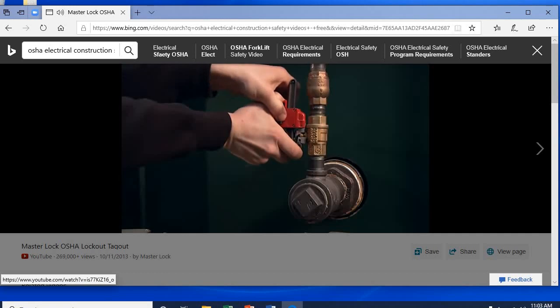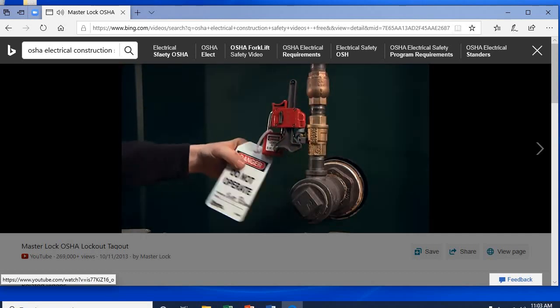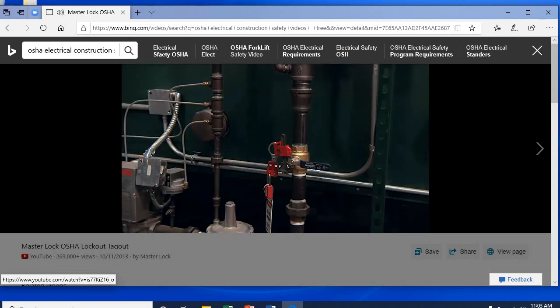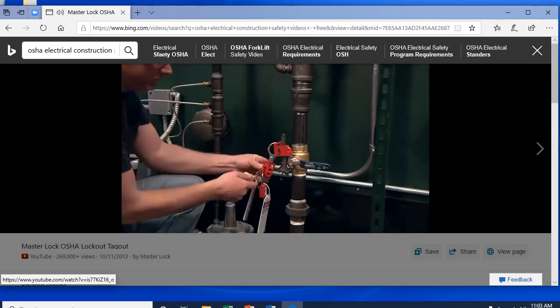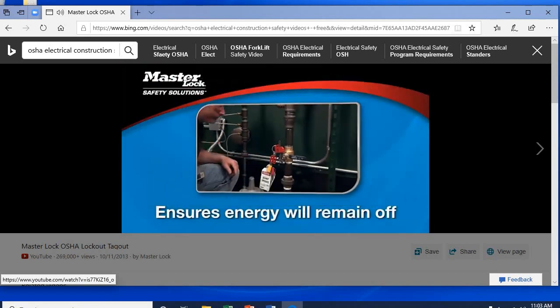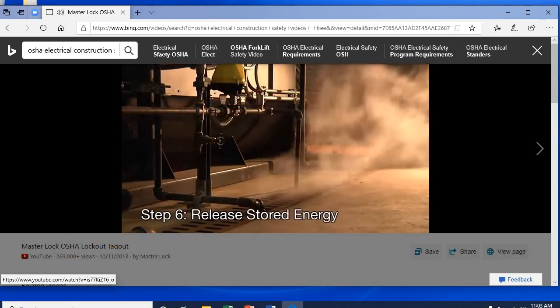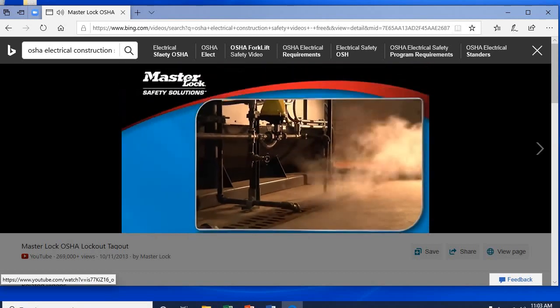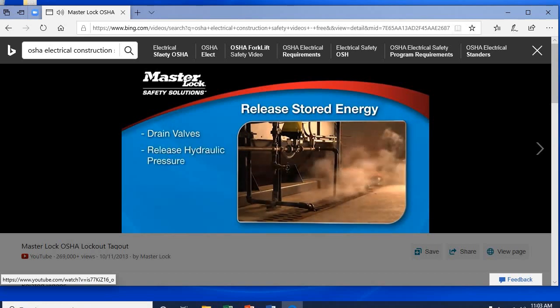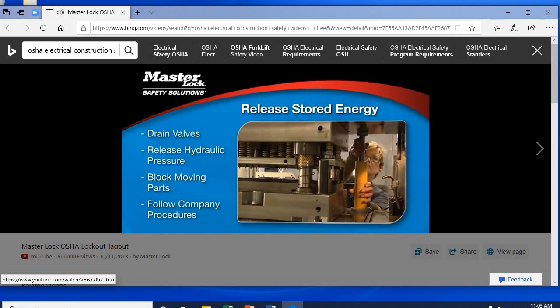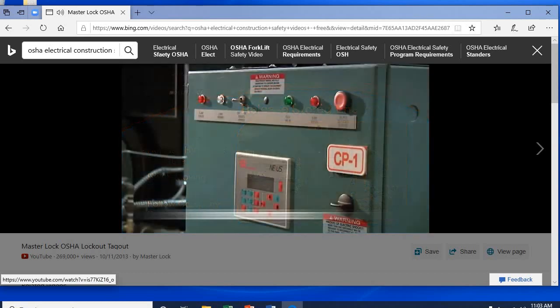The lock or tag that goes with it must clearly indicate who applied the lockout device. If several people are going to work on a piece of equipment, each one must apply his or her own lock to the isolation device. This ensures that the energy source will remain off until each employee removes his or her lock. Step 6. Release or secure any stored energy. This may involve draining valves, releasing hydraulic pressure, blocking moving parts, or however it's detailed in your company's procedures. Step 7. Verify the power is shut off by trying to restart the machine. Once verified, return the machine's switch to the off position.